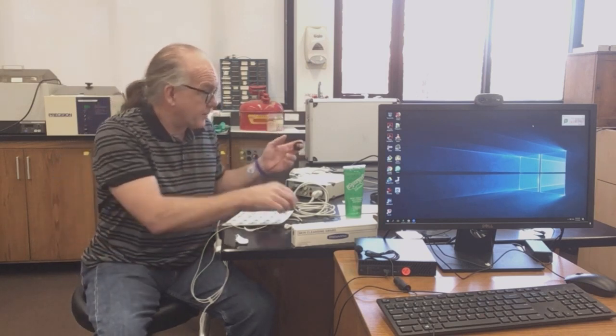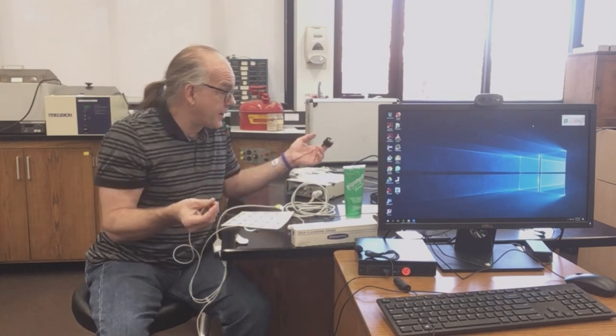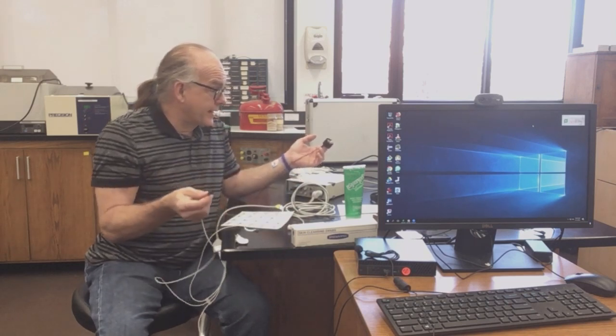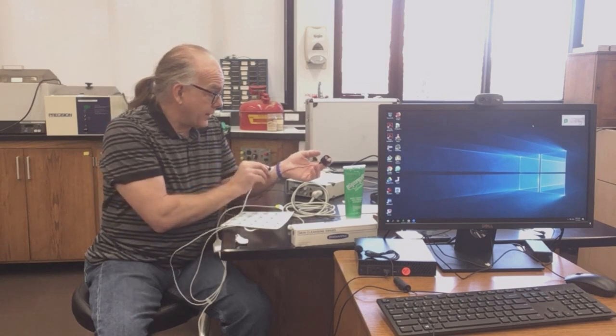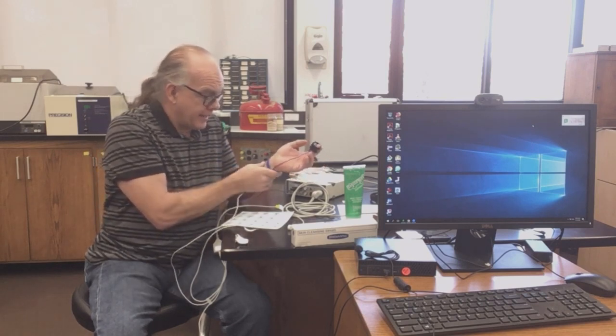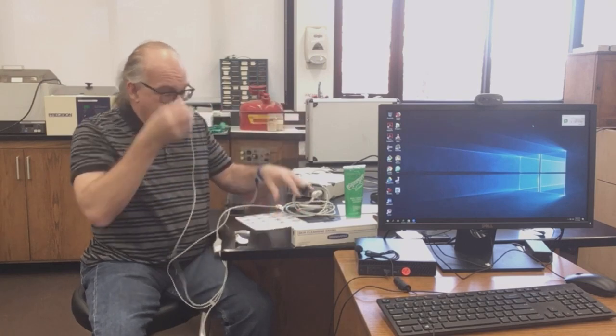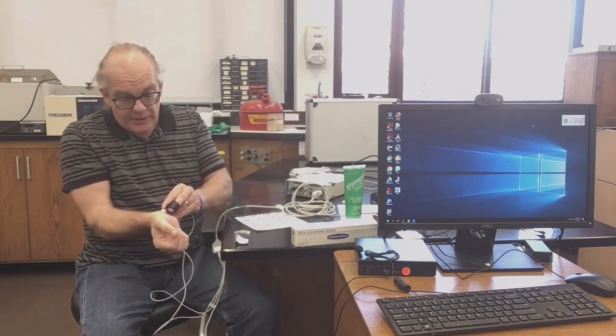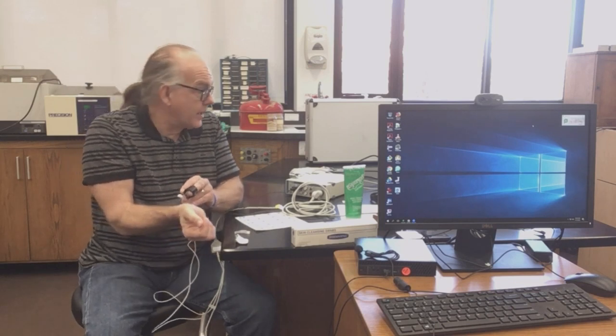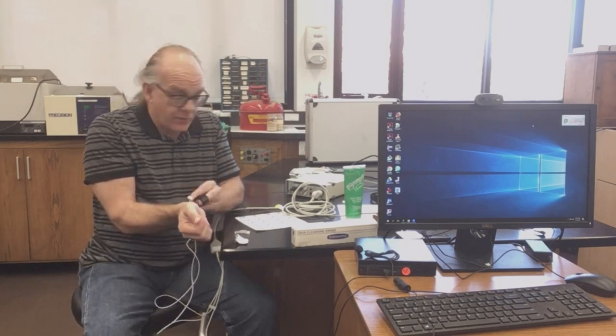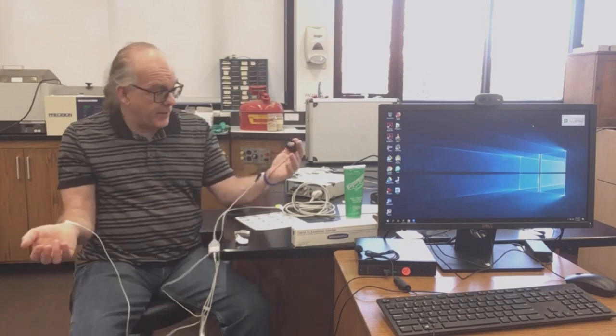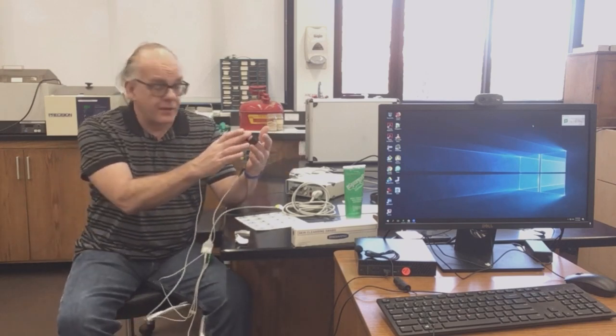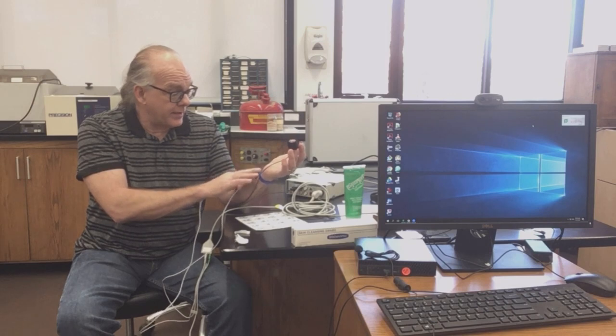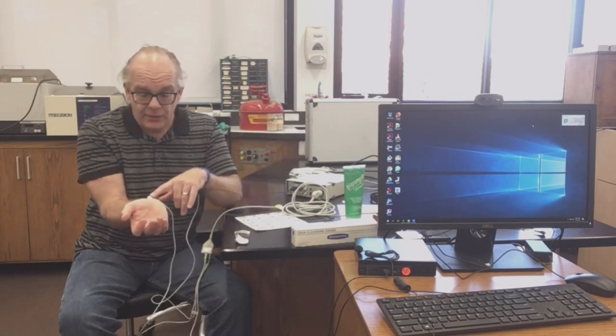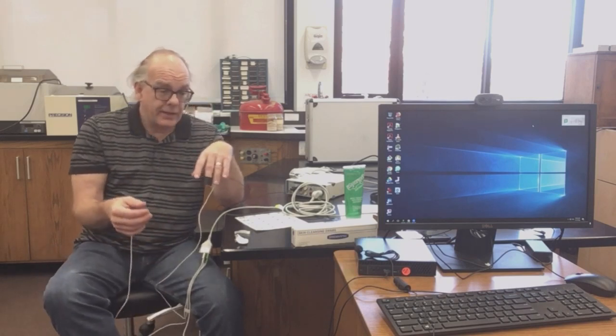So once your subject has been prepared, we've got the electrodes attached. We are going to attach the black electrode to the left forearm. I'm going to snap that in position. And then the white electrode is going to go on the right forearm. And so we basically have everything hooked up. We've got the pulse transducer on the finger, the black electrode on the left wrist, the white electrode on the right wrist, and I've got the dry earth strap on my right ankle.